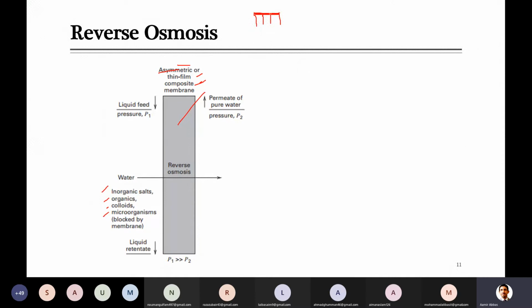Macroporous membranes have very large pores and are not used for separation, but that material is just used as a support. If we put just this small thin layer, which can be as thin as a paper sheet, under high pressure, and I told you that pressure can be 30 to 50 bar in these kinds of systems where you are cleaning seawater, then that small top separating layer, that thin film, cannot sustain that pressure.